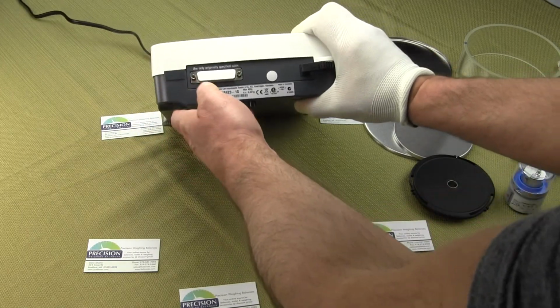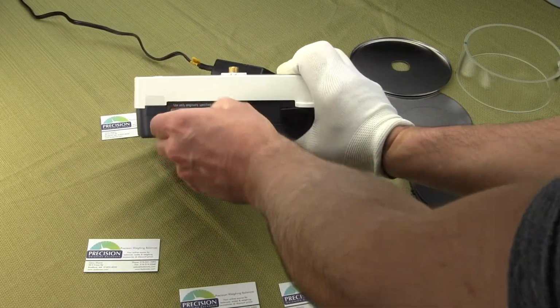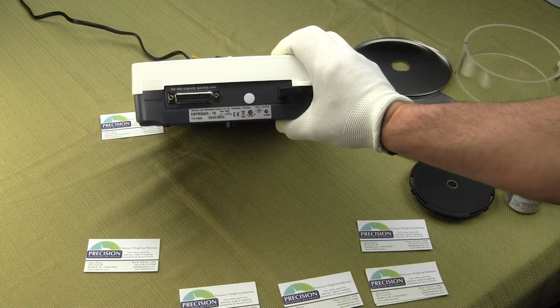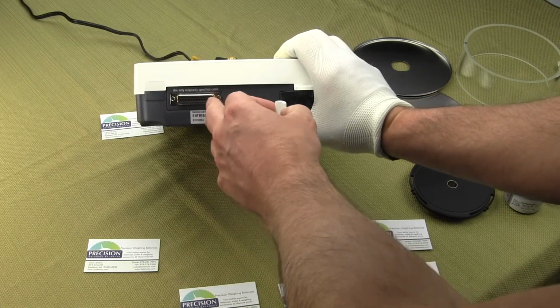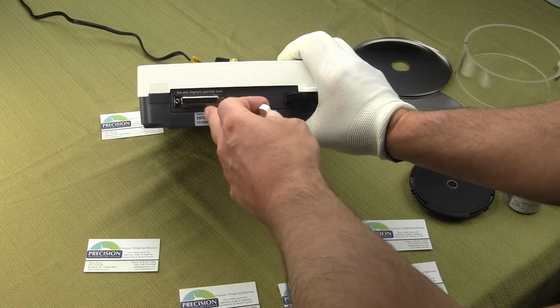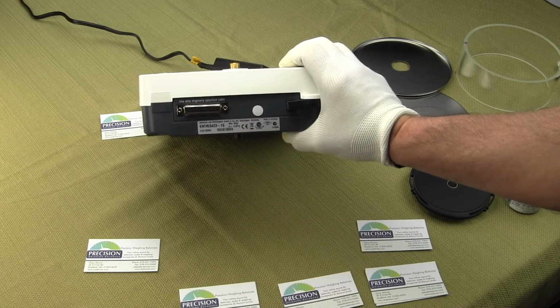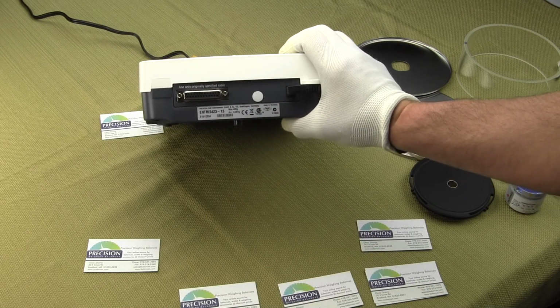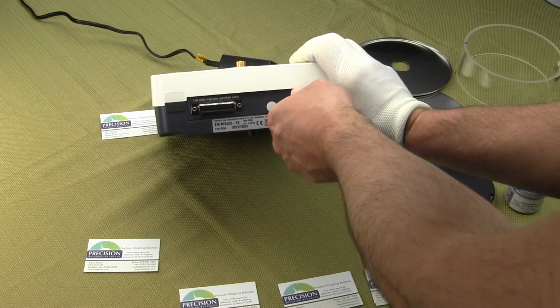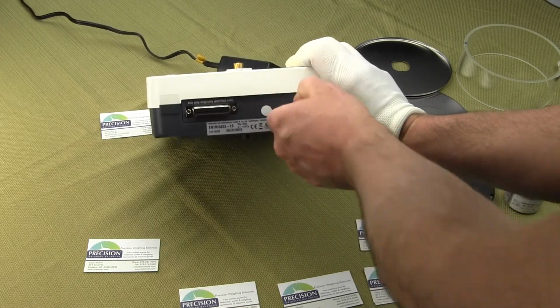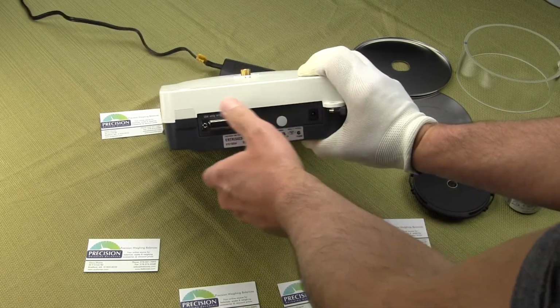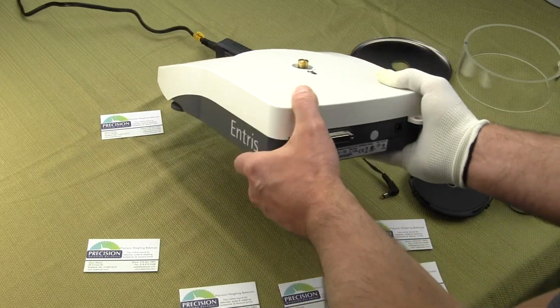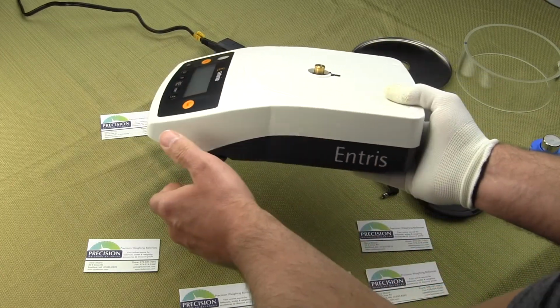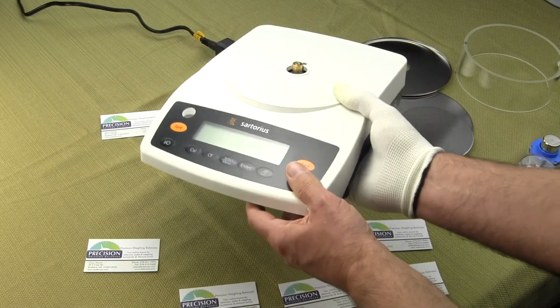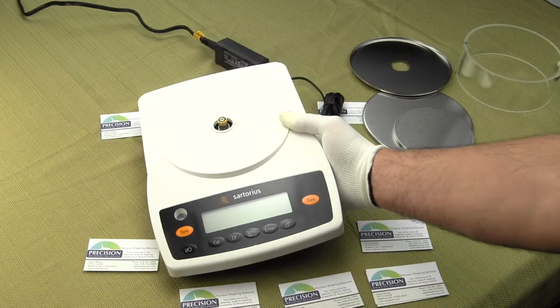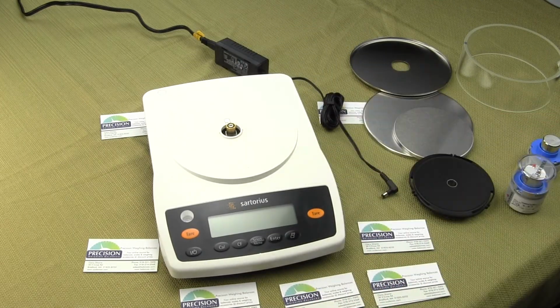On the back of the balance, we have an RS-232 interface. This would be used for sending data to a PC. You'd have to buy the optional cable, or Sartorius's printer, which is the YDP-20. On the back we have your AC adapter that comes standard with all these balances. This balance does not operate off of batteries. It's AC powered only, and that really sums it up.